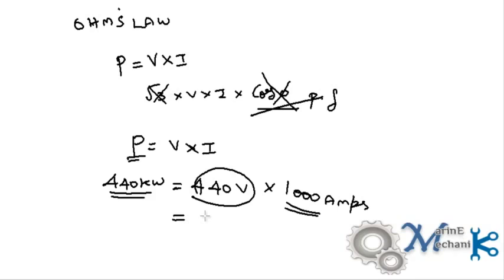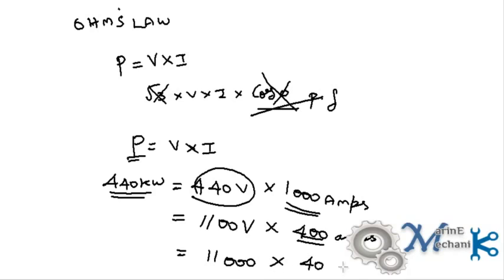Now let's say I operate the ship at, for example, 1100 volts. The required amperes drops to 400 amps. That's fantastic, so I just need to design the cables for 400 amps. And if I increase the voltage to 11,000 volts, the required amperes is just 40, which is even less. So what we find is that by increasing the voltage, the current drops for a given power on board a ship.